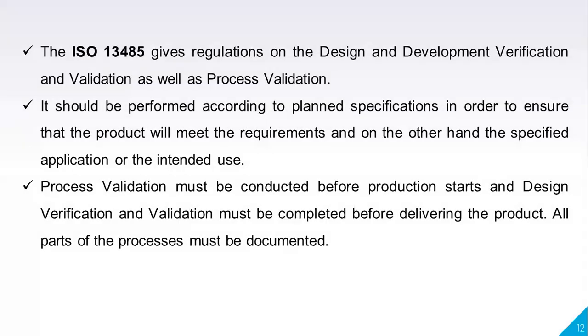Then another one, the ISO 13485. That is the minimum requirements for a medical device establishment. It also gives regulations on the design and development of verification and validation as well as process validation. Not only the European EU MDR, not only FDA's 21 CFR 820. Apart from that, ISO 13485 also gives some regulations on design and development verification and validation. So these three are very important, you have to remember, right?